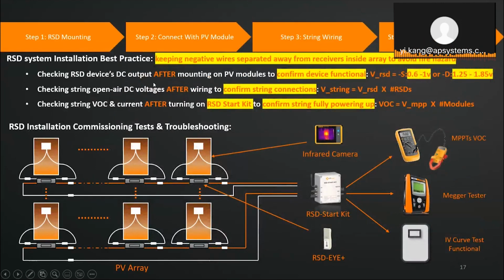So when you connect this panel, if you want to make sure your panel is functional, just directly use the DMM to measure its output voltage to get this value. Then when you connect the output into the full home run, before you connect to your string inverter, you need to test the open-air DC voltage by using this value times how many devices you have. For instance, if you have 10 panels in one string, when you're testing the open-air DC voltage, you will probably get between 6 and 10 volts.